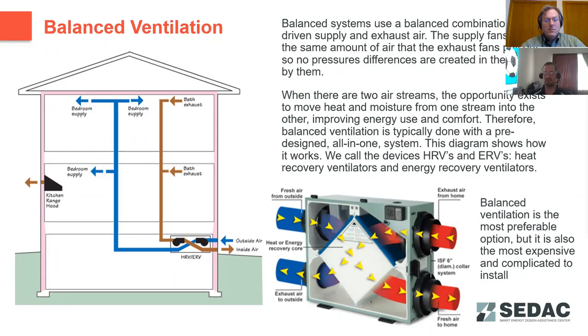The one thing we do like to point out is if you're going to install one of these, it does require maintenance. The filters have to be changed on the heat exchanger. You want to put it somewhere where the occupant is going to know about it and be able to do those filter changes and regular maintenance on the system. If you put it in a crawl space or an attic where it's hidden and forgotten, it's very likely that somewhere down the road there's going to be an issue with that system where it's not going to work properly, and then you're not going to have your design ventilation for that building.